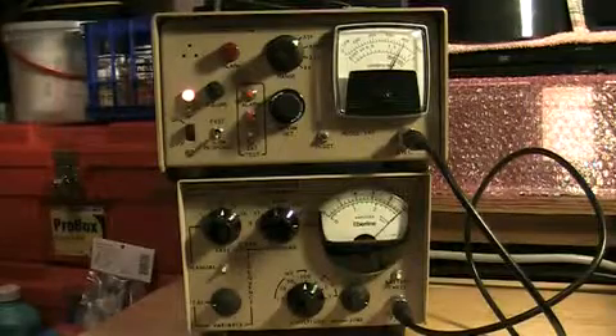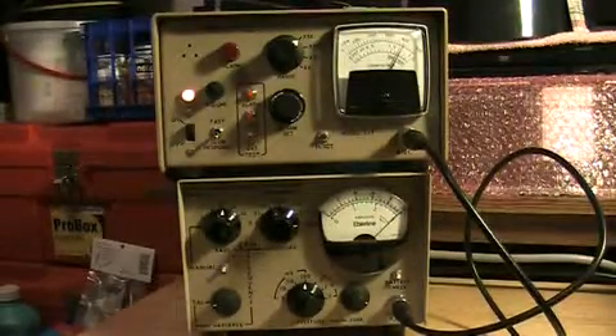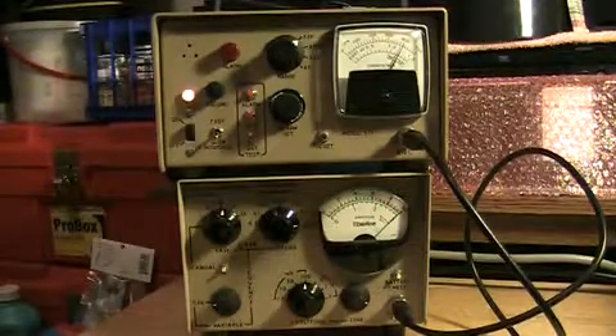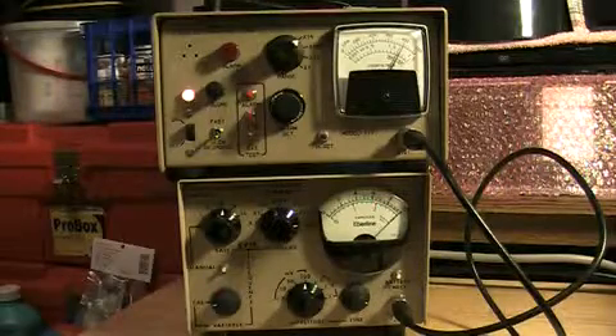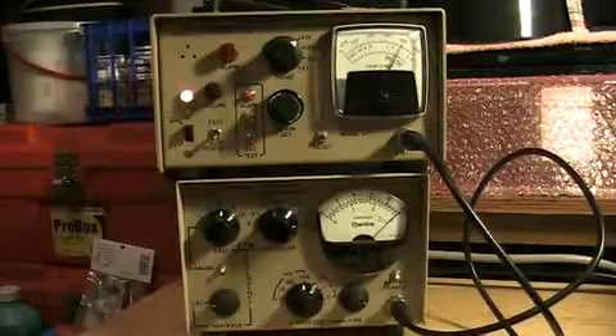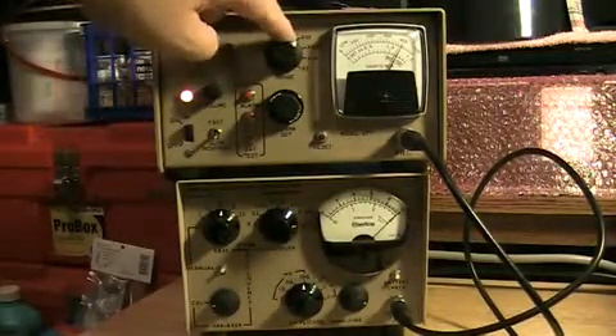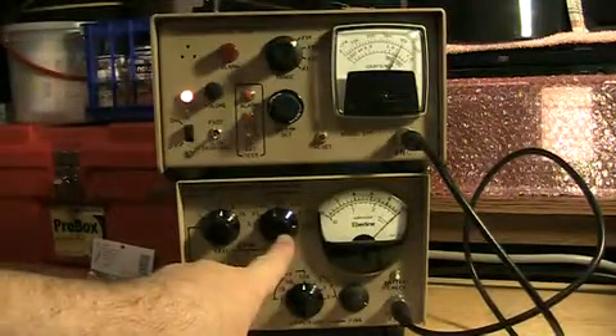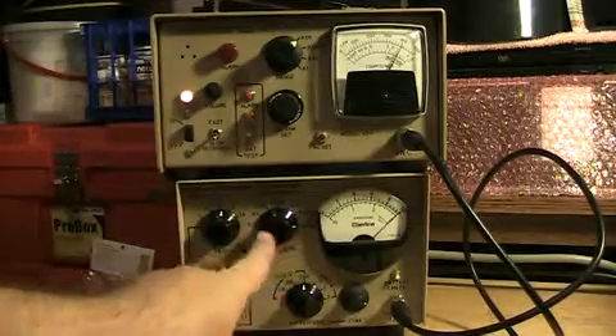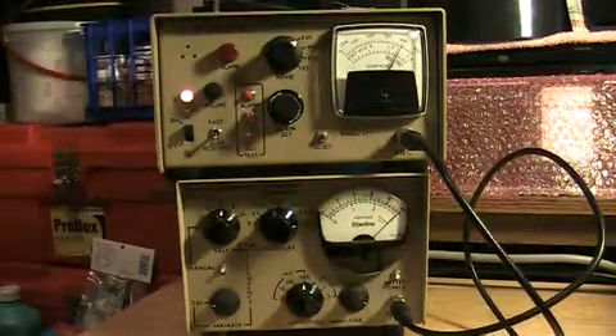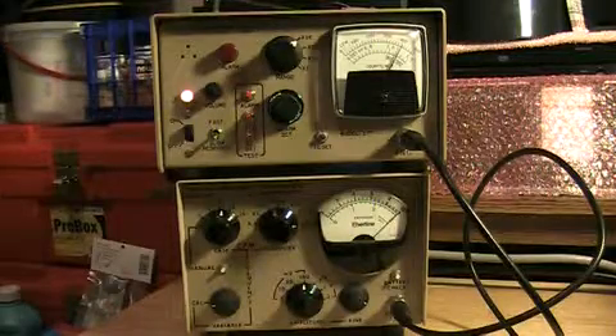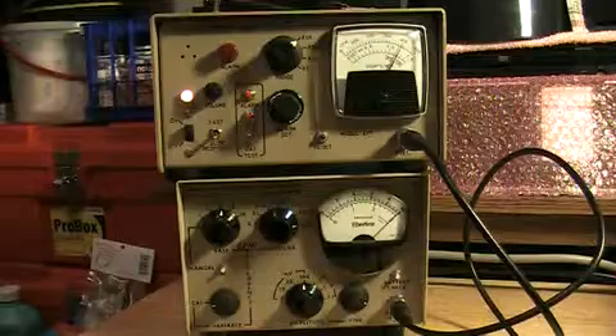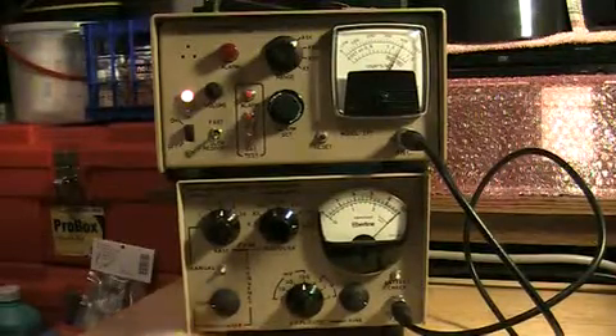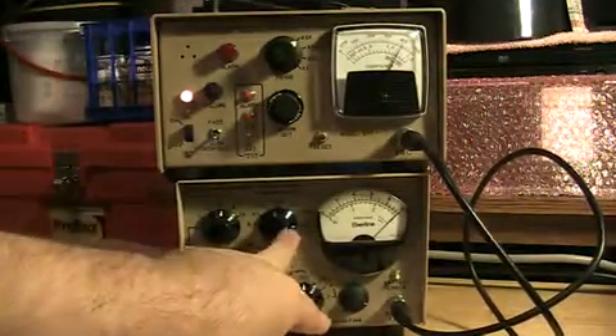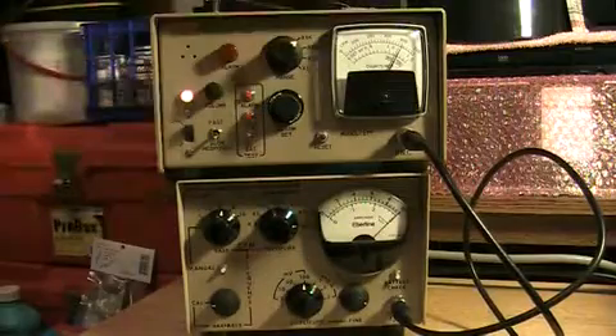Okay, it's hard to get this exactly centered on the meter. That's pretty good. There's still some parallax. But when I calibrate these, I start at the highest scale and work down. So here I'm on the ×1000 scale, and also ×100, ×4, 100K. So that gave me the 4 level here. Okay, sometimes it's hard to get this camera centered right on there onto the bezel of the meter. So there may be some parallax. But the way this is set up with the counts per minute, a rate of 4 × 100K, this range here should be right at the 4.